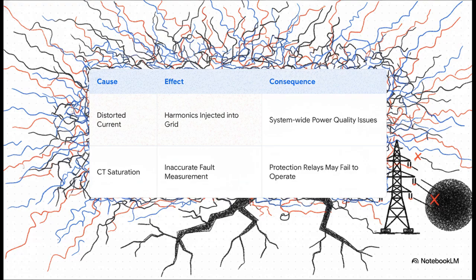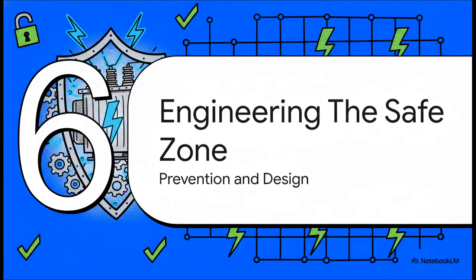And to hammer the point home, if a current transformer saturates during a major system fault, the protective relays get bad information. They might fail to trip the breaker, and that's how a simple, containable fault can cascade into a widespread blackout. So given how truly awful the consequences are, it's no surprise that the entire field of power engineering is built around one simple goal: keep transformers out of saturation. This isn't about cleaning up a mess. It's all about prevention through clever design and smart operation.